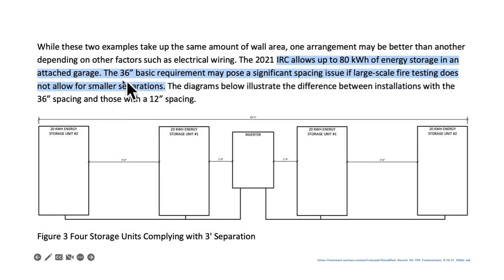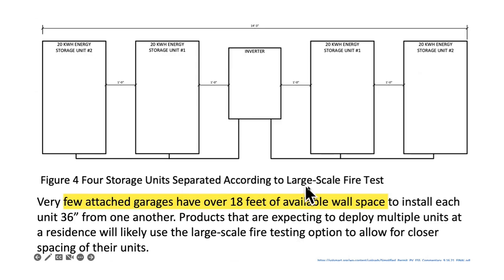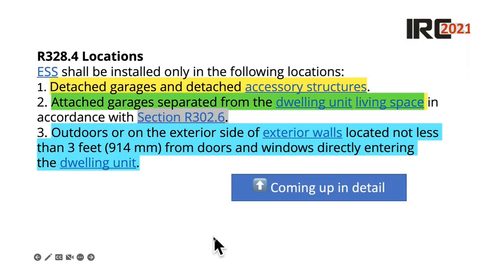But if you had to do those 3 feet, if they didn't do the large scale fire testing, you have the width of the energy storage system itself. You have the 3 feet between each energy storage system. And pretty soon you're talking about 18 feet, 3 inches is what we have for this example. So find a garage with that much space on the wall, and you'll be really lucky to find that. And so after the large scale fire testing, we could put them closer together, of course, and then you can find places to put them on the wall.